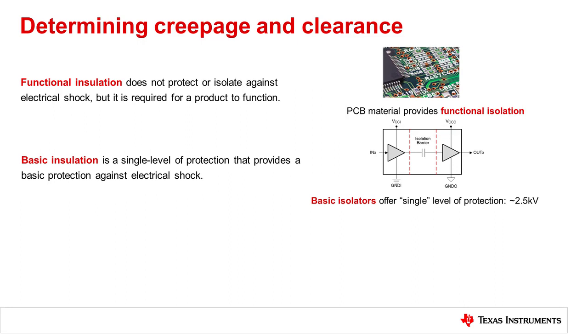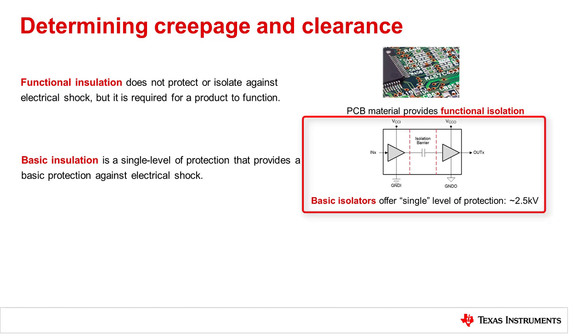Basic insulation is a single level of protection that provides basic protection against electrical shock. A very common example would be the plastic insulation of an electrical cord, which is a single level of protection from AC voltages. If the basic insulation fails, there is exposure to hazardous voltage. For integrated circuit isolators, the term basic isolator is used to describe isolation that acts as a single level of protection for voltages typically between 2.5 to 3 kV and occasionally as high as 5 kV.